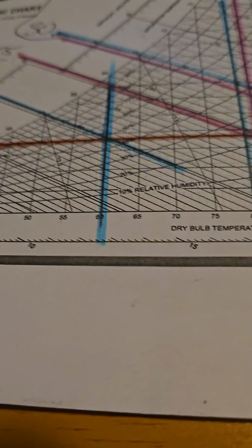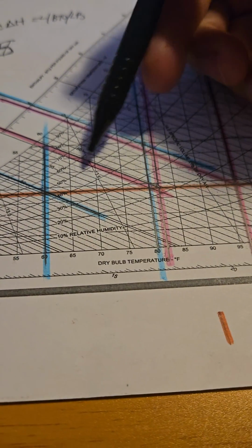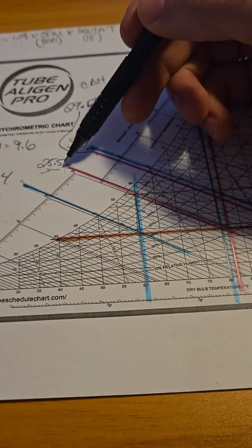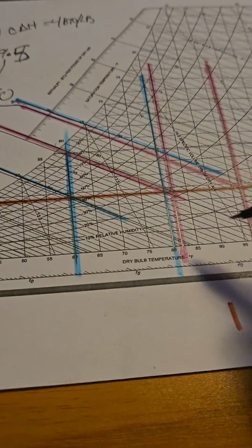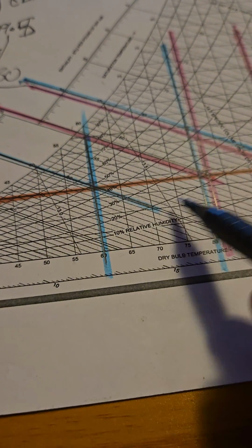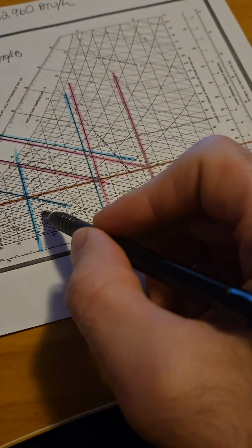All you need is 2 points, and you can calculate everything in psychrometrics. So, for example, we have our grains, and we have this, which gives us our point. From that point, if we go diagonally, that gives us our wet bulb, and it gives us our BTUs per pound. If we go to the left side of our grain line, that's our dew point. And if you notice these relative humidity lines that curve up, if you follow that, here it's between 20 and 30. Let's say it's like 24% relative humidity.